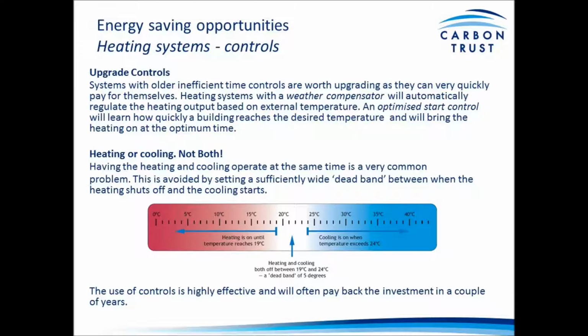Make sure your heating and cooling systems operate with an effective what we call dead band of temperatures. For instance, this gives guidance that heating should not come on once internal temperatures exceed 19 degrees, and cooling should not come on until internal temperatures exceed 24 degrees. Now, between these two temperatures, no heating or cooling takes place, and you would be surprised just how often the space within your building will remain between those temperatures without any external or artificial heating and cooling.